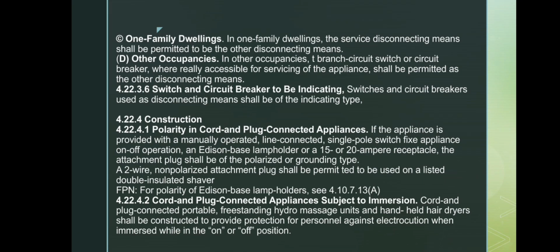Next slide, we tackle one-family dwellings. The service disconnecting means is allowed to serve as the disconnecting means for appliances. In other types of buildings, the branch circuit switch or circuit breaker may be used as the disconnecting means as long as it is readily accessible for servicing the appliances. Switches and circuit breakers used as disconnecting means must be the indicating type, meaning they clearly show whether they are on or off.